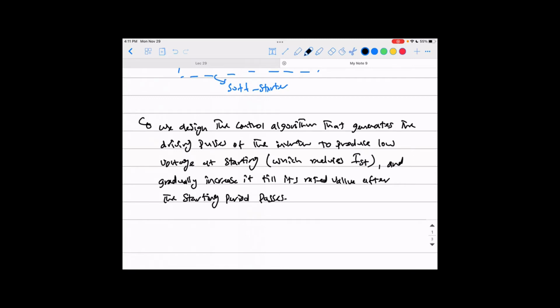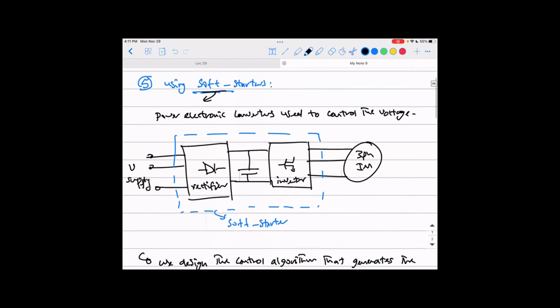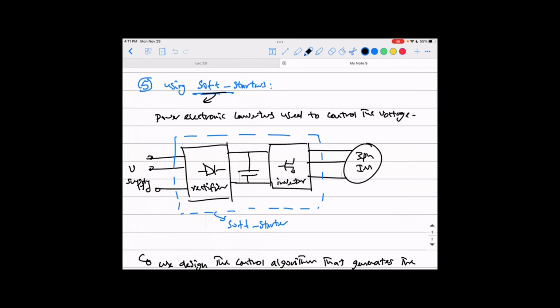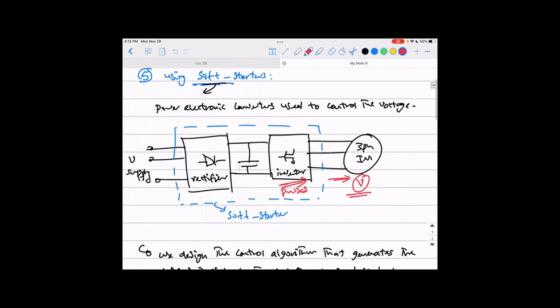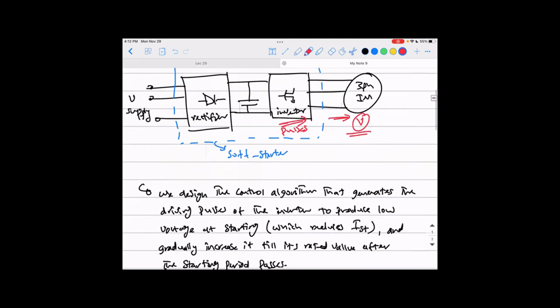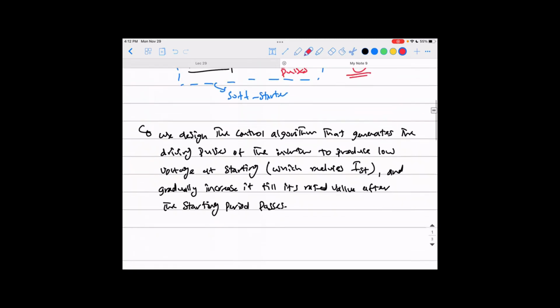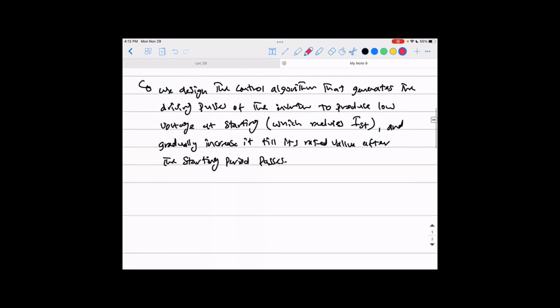passes. Okay, so the same idea we used before with controlling the speed of the motor. Remember when we said we can control the frequency and the voltage output of the inverter, which is basically going to the motor here. But here we are not more concerned about the frequency, we're more concerned about the voltage of the motor. This one can be controlled by controlling the pulses that are going to this inverter. So what we do is we start the motor with a low voltage, and this will reduce your starting current, and gradually control the inverter pulses to increase the voltage applied to the motor until you reach the rated value when you pass the starting period. And that's basically what you do. Okay, that's why we call it soft starters, because we gradually increase the voltage.